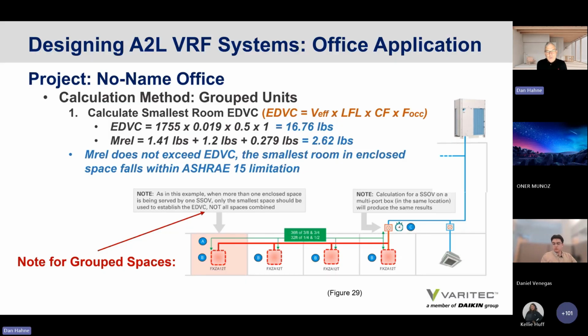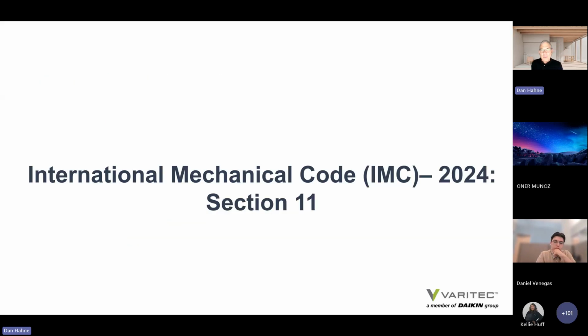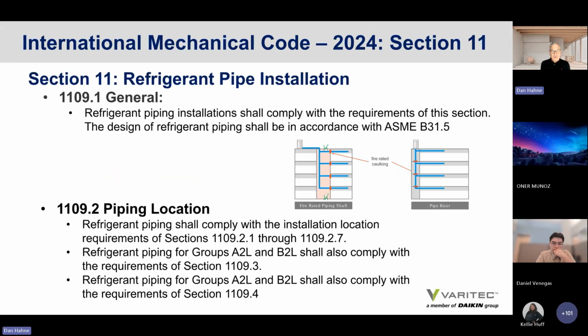refrigerant charge for grouped offices served by a common circuit. And if you run the math and calculations, you can see that by using shutoff safety valves, you can meet the refrigerant concentration limits as well. But this gives you an idea of how to run these calculations to see whether or not your design is meeting conformance. So what does the International Mechanical Code have to say about variable refrigerant systems?